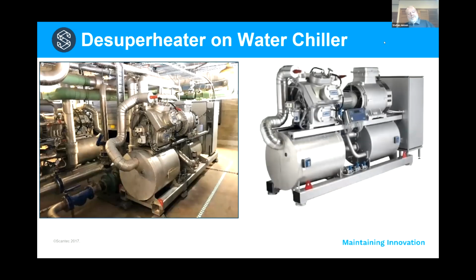So here's a little photo of the first example. These are 2 water chillers, 600 kilowatts cooling capacity each. They produce chilled water, standard air conditioning temperatures from 12 down to 6 degrees. You can't quite see the desuperheater here. It's just a little silver thing that sits on top of the compressor. I don't know whether you can see my cursor on the other end, but it's a little thing about 1 meter long by about 100 millimeters diameter, sitting right there above the compressor.